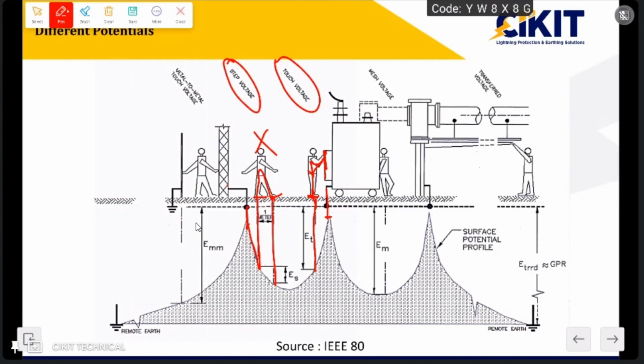One is step voltage and touch voltage. The other parameter is metal to metal touch voltage. In this case, the person is having contact with one structure which is at a higher potential, and he is making contact with another structure which is at another potential. Because of this difference in potential, the current will flow from the high potential structure to the low potential structure through the body of the person. So here also the main damage is caused because of the difference in potentials.